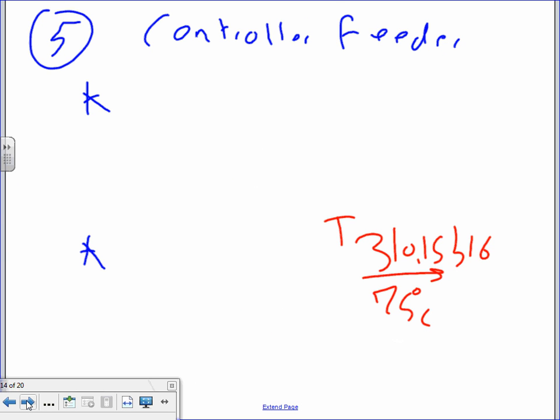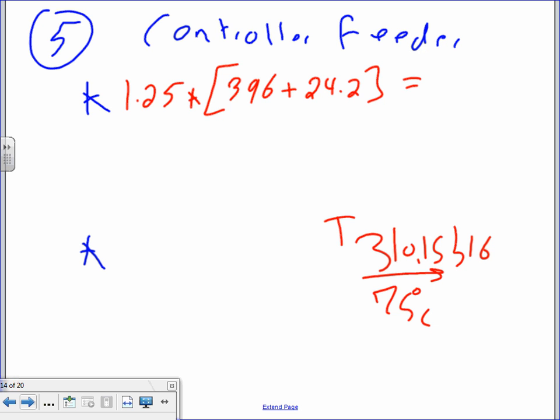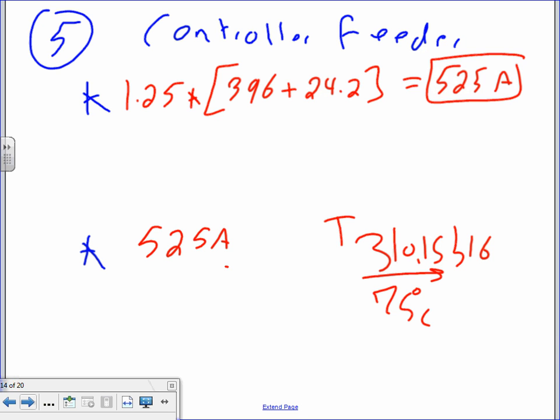Okay. Controller feeder, number 5. We're going to go find the controller feeder. The first thing you need to do, guys, is multiply by 1.25 continuous load. Add the 2 together, like we've done. 396 plus 24.2. That'll get you 525 amps. A healthy 525 amps. Then you have 525 amps. You're going to parallel them, obviously. 525 divided by 2 to parallel. That will get you 263 amps.